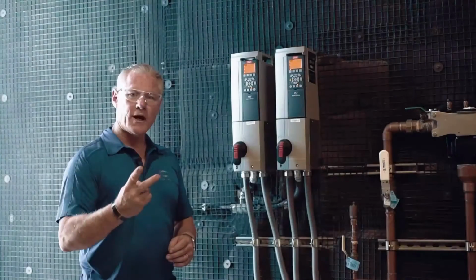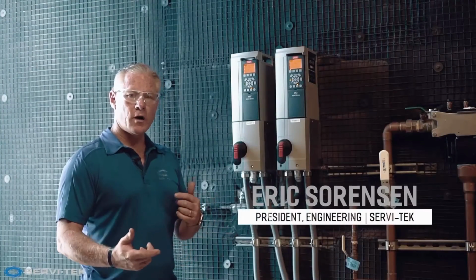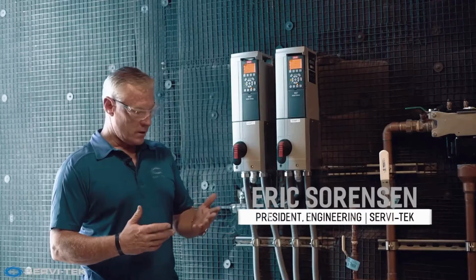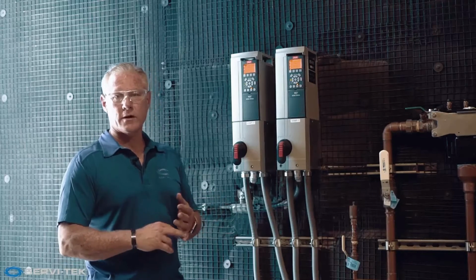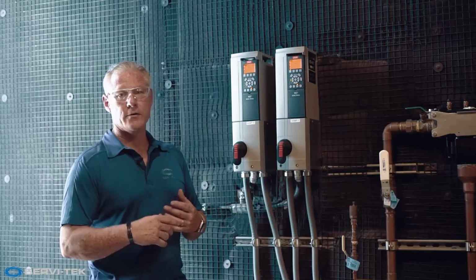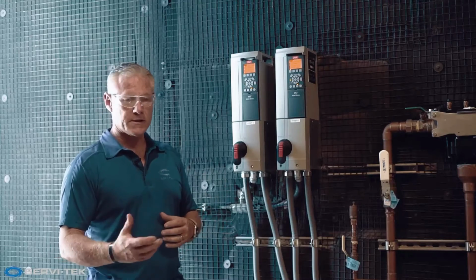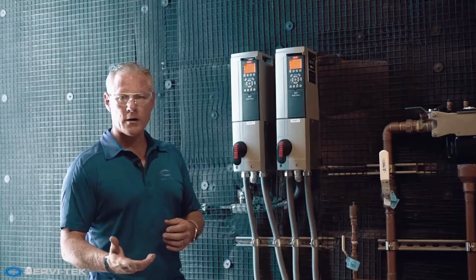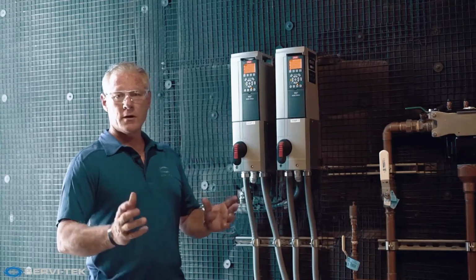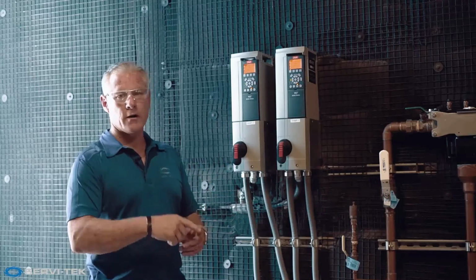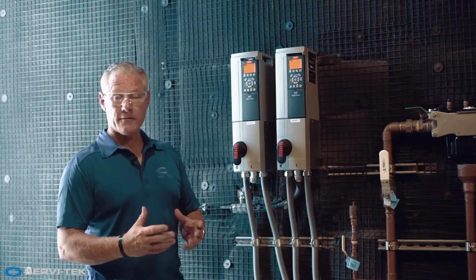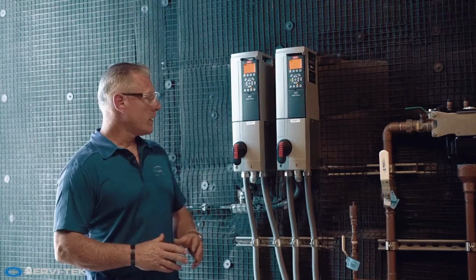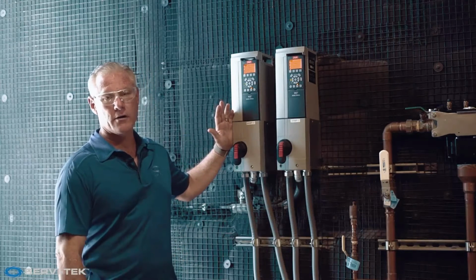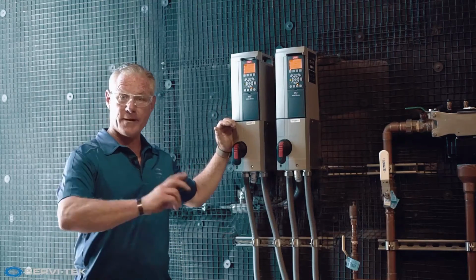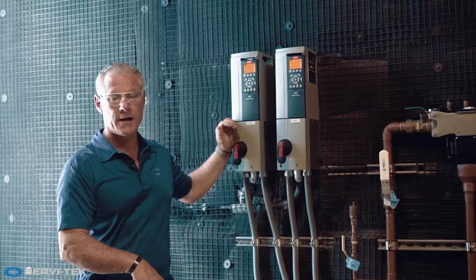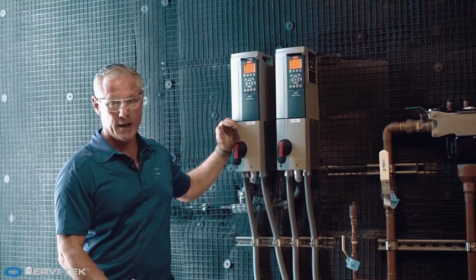So remember, we have two types of hot water running through our typical office building. We've got our domestic hot water. That's what we're going to see at the sink, in the bathroom, or in the kitchens. That's just regular potable water, city water that's coming through, going through a hot water heater, and then being pushed out at the sink level. Then, of course, we have high temperature hot water that's running at about 175 to 190 degrees, versus about 120 degrees on the domestic side, for comfort heating.